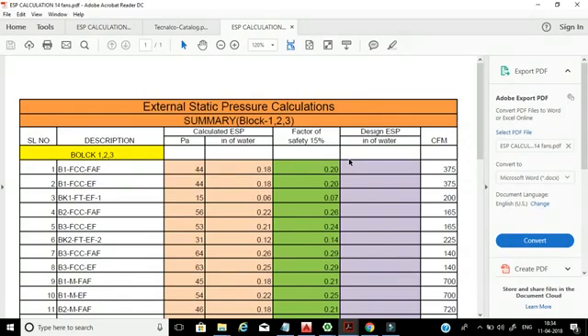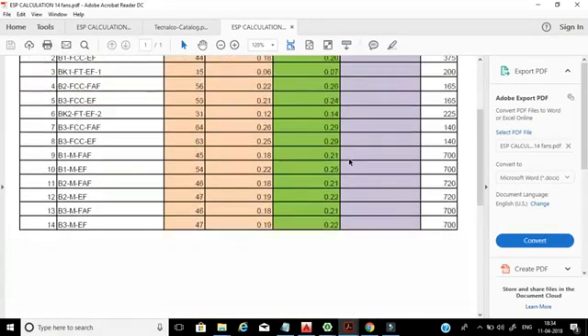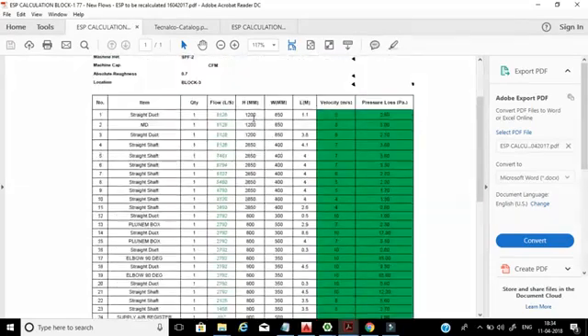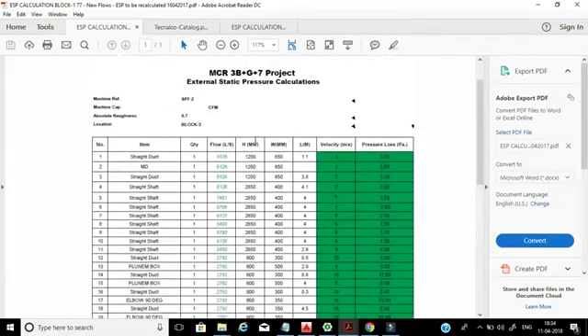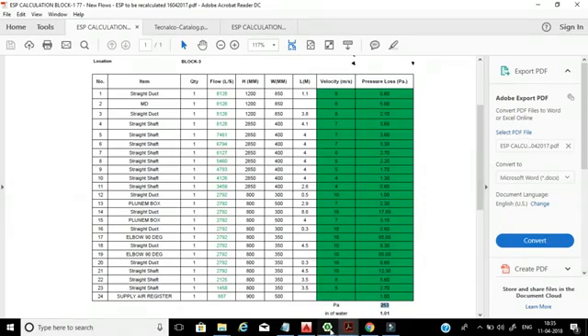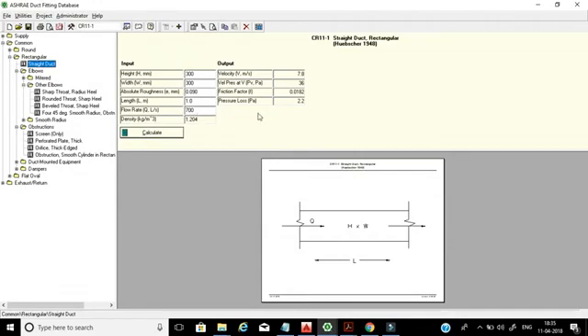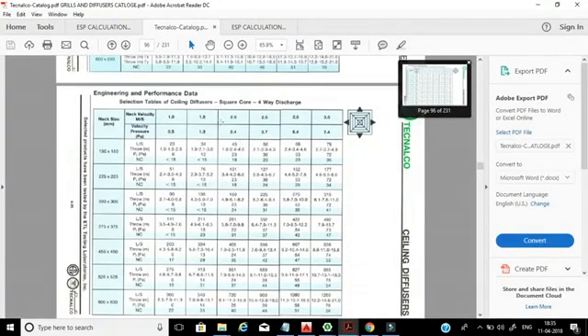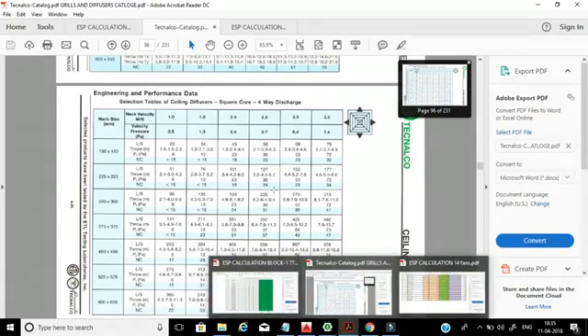While submitting the ESP calculation, there are some things that need to be attached: a front page, a summary sheet, and all the calculation pages — one page per machine. Also, there are attachments like the straight duct results from the software and data sheets. Now we understand what needs to be attached with the ESP calculation, so now we will calculate in our software, the ASHRAE Duct Fitting Database. First we need to open this drawing.